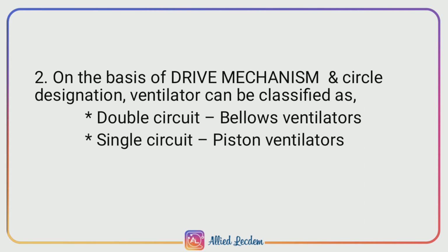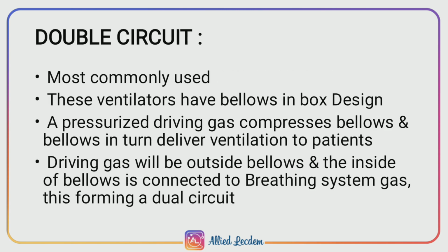Ventilators can be classified as double circuit, bellows ventilator, single circuit, and piston ventilators. Double circuit means that the driving gas, which is pressurized O2 and air, compresses the bellows, which empties its content into the patient. The driving gas will be outside the bellows, and the inside of the bellows is connected to the breathing system. These are most commonly used.